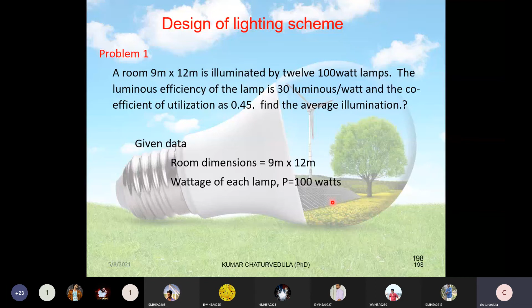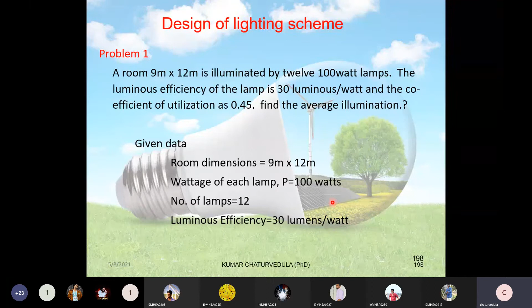Okay, so as usual, given data: room dimensions are given as 9 meter into 12 meter, wattage of each lamp is 100 watts, the total number of lamps available is 12, the luminous efficiency is about 30 lumen per watt, and the utilization factor is given as 0.45. What you require is average illumination. So to find average illumination, what is the formula?